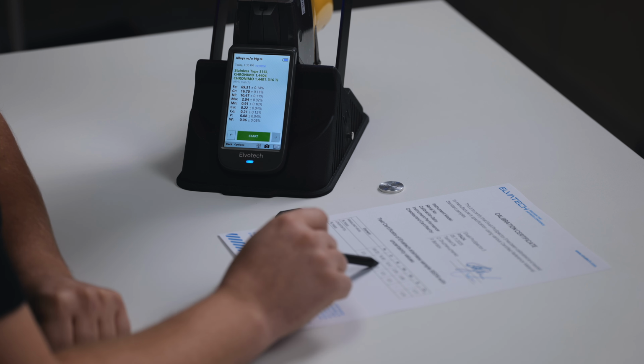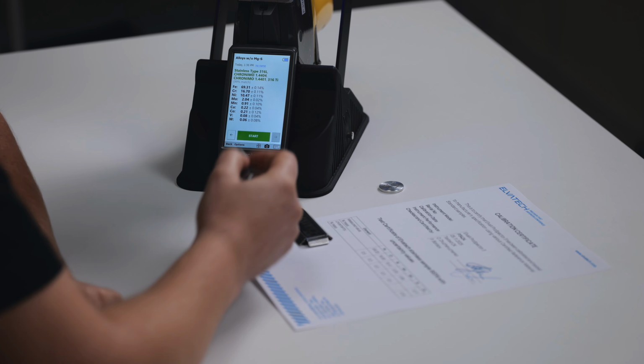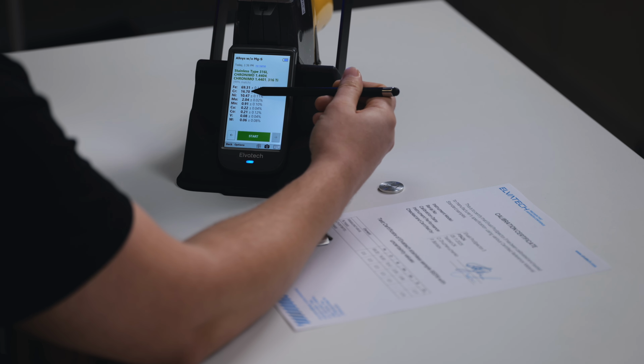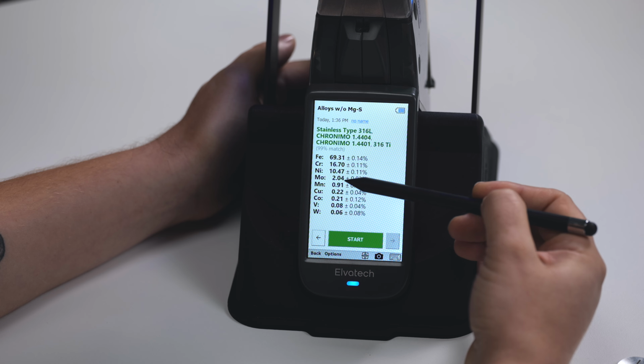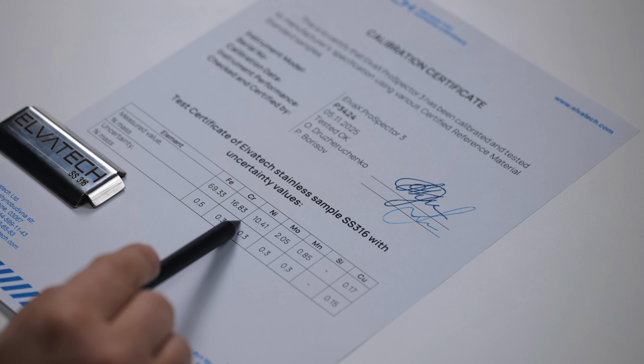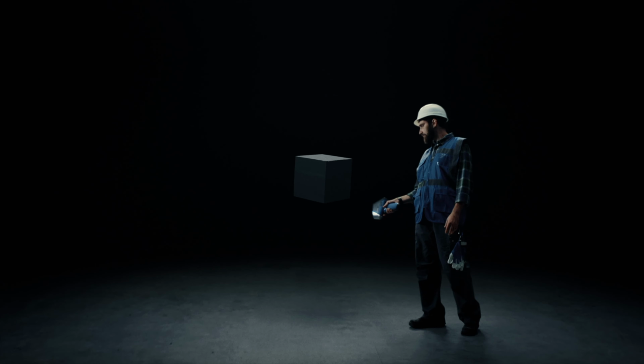Then compare the measured values with the ranges given in the calibration certificate that is supplied with the sample and the analyzer. If the results go significantly outside the ranges given in this certificate, this is a clear signal that you need to perform energy calibration. You don't need to connect the instrument to a computer. Everything is done directly from the analyzer's menu. Now I will show you in practice how to perform this procedure.